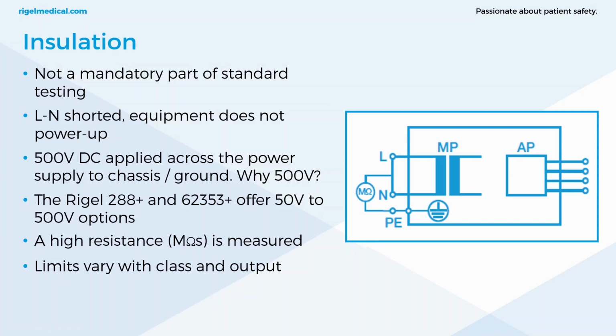Insulation testing is not a mandatory part of testing, certainly not in NFPA 99 or many of the other standards and codes, although it is in the Australian version; in most standards, that's not the case. Now here a high resistance is more beneficial because you're measuring the isolation between the conductive parts of the circuit and the enclosure. Now our devices have different voltage ranges, and that's to test non-standard voltages, so anything that's got safety extra low voltage equipment, DC power supplies, etc., has got that option to test at lower voltages.